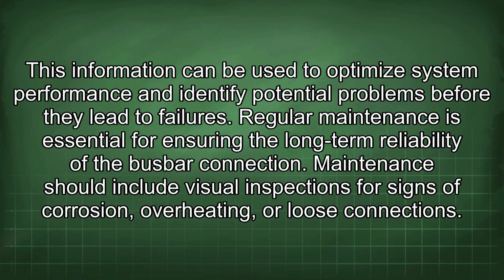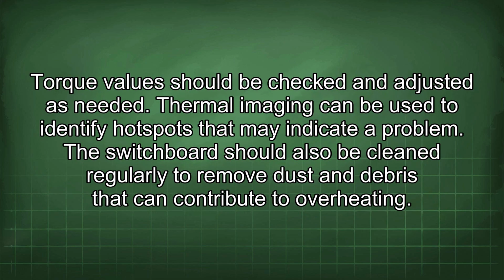Regular maintenance is essential for ensuring the long-term reliability of the busbar connection. Maintenance should include visual inspections for signs of corrosion, overheating, or loose connections. Torque values should be checked and adjusted as needed. Thermal imaging can be used to identify hotspots that may indicate a problem. The switchboard should also be cleaned regularly to remove dust and debris that can contribute to overheating.